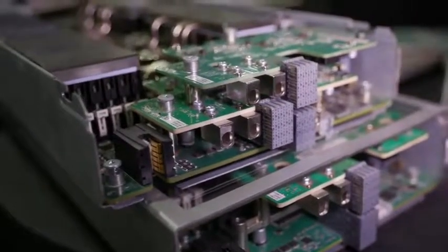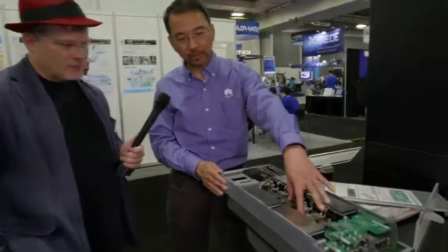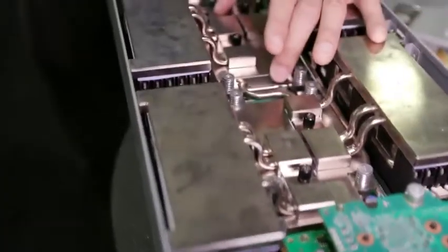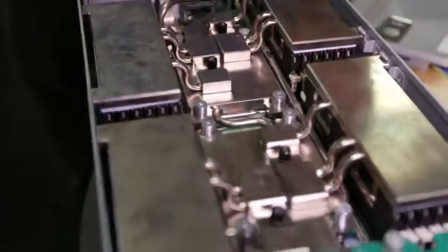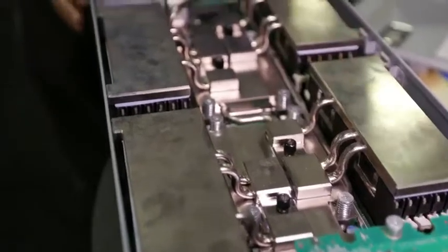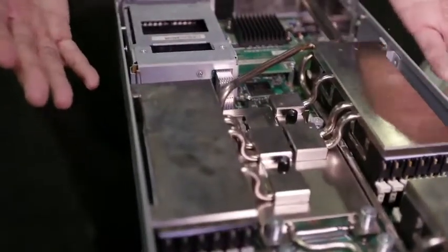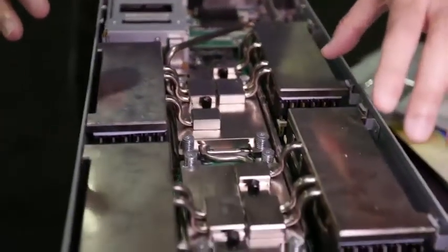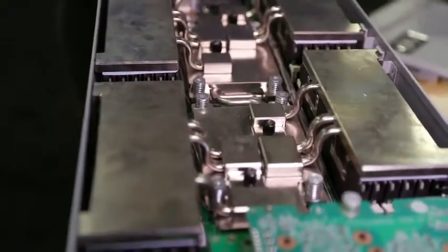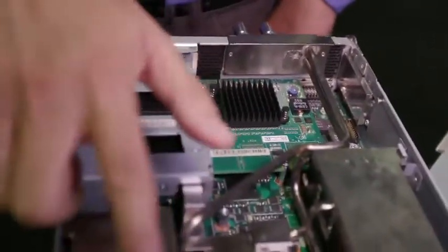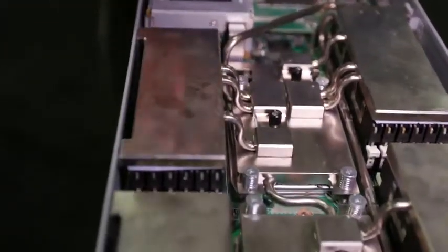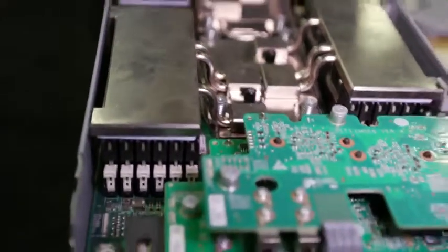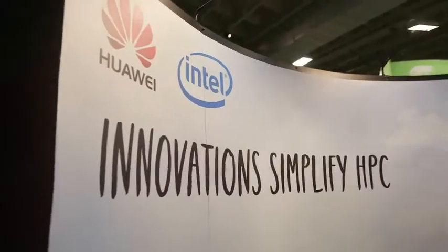Francis, you've pulled out this module here. What are we looking at? There's a unique design characteristic about our liquid cooling technology. Here you can see the cold plate covering the heat elements, mainly the CPU, all the memory DIMMs, and the voltage regulator modules, which represent about 80-85% of the heat dissipation of the system, on a very nicely designed metallic component. The uniqueness is that all this tubing is a single tube with no joints, continuous within the system. The only joints are on the front input connector, so it dramatically reduces the probability of leaking.